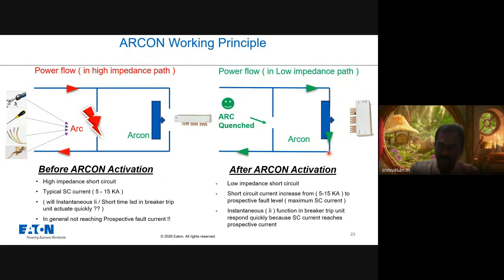Also, every time the ARCON has been actuated, it needs to be replaced. It acts like the airbag in a car. As long as the car does not have any big impact, the airbag will stay intact. But if a car hits another car or a pole very fast, the airbag will be actuated, and then you need to replace the airbag. In a similar way, once the ARCON has been activated, we need to replace it with a new one. Replacing the ARCON and simple cleaning inside the affected compartment can all be done in less than 45 minutes.